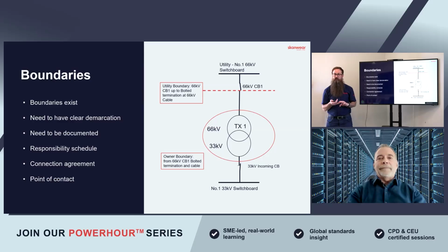This is something I see so often, where we've got joint bits of equipment, such as battery tripping units. You might have a battery tripping unit on the circuit breaker in the DNO's or utility substation, which actually belongs to you as the owner, and the assumption is made that the utility provider is maintaining it. But in the event of a fault, you need to make sure that battery tripping unit is actually going to trip that circuit breaker. So you've got to make sure responsibilities are clearly defined and that people are maintaining things like this, because I see this happen very often.